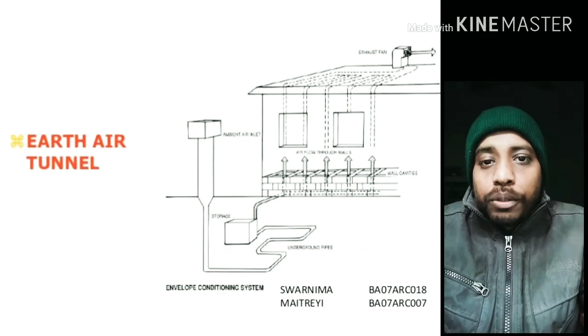At the data center, Aircel built an innovative earth-air tunnel system to provide cool air for air conditioning units, needed to control the temperature within the server room that tends to heat up. This system consists of 4 sixty-meter pipes buried about 5 meters below ground, through which air is pulled out for cooling the air conditioning units. Since the temperature below ground is invariably cooler than the air temperature, the cool air reduces both the water and electricity needed to cool the room.